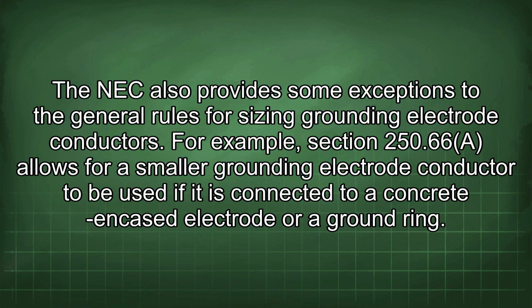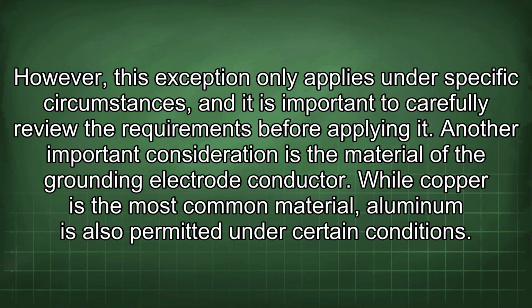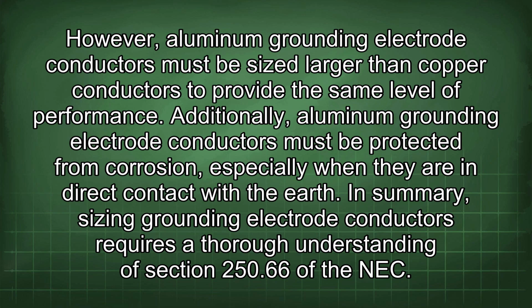For example, section 250.66 allows for a smaller grounding electrode conductor to be used if it is connected to a concrete encased electrode or a ground ring. However, this exception only applies under specific circumstances, and it is important to carefully review the requirements before applying it. Another important consideration is the material of the grounding electrode conductor. While copper is the most common material, aluminum is also permitted under certain conditions. However, aluminum grounding electrode conductors must be sized larger than copper conductors to provide the same level of performance. Additionally, aluminum grounding electrode conductors must be protected from corrosion, especially when they are in direct contact with the earth.